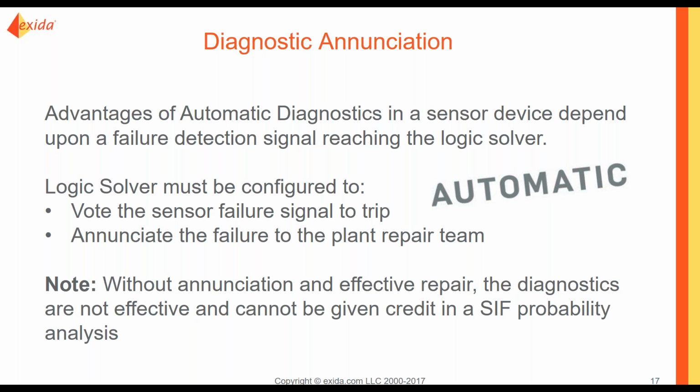The logic solver must be configured to either vote the sensor, so it will signal to either trip or to annunciate the failure to the plant repair team or the operator, so that a repair team can make a repair and the failure can be restored back to the correct operating conditions.